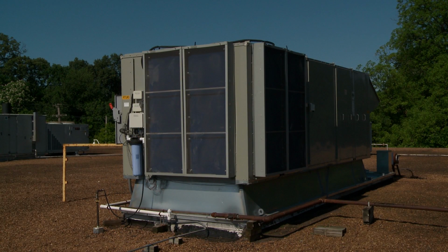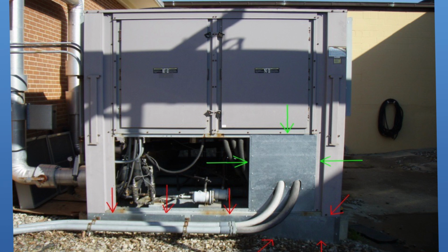In order for the Evaporcool system to save the most energy for your customer, all air flowing past the condenser coils must pass through an easy frame. Before you complete the plumbing and install the Evaporcool easy frames, you must identify locations for field-supplied sheet metal close-offs to ensure this airflow occurs. It is ultimately up to the installer to identify where and how much sheet metal to install, if any at all. The layout diagram should give enough information for the installer, but Evaporcool Engineering can provide assistance if there are any specific questions about where to place sheet metal.